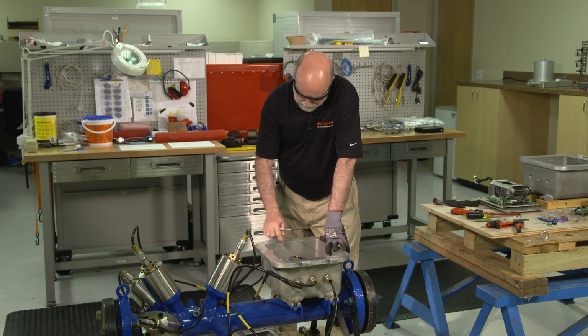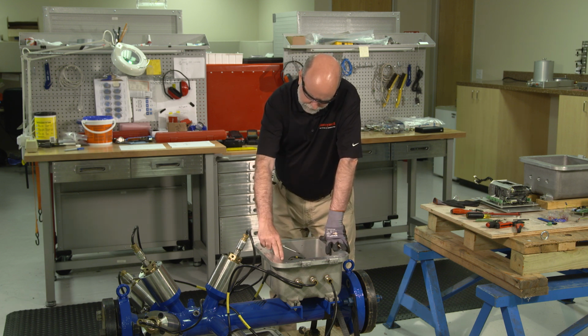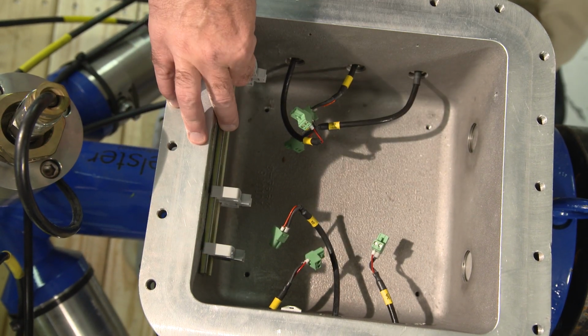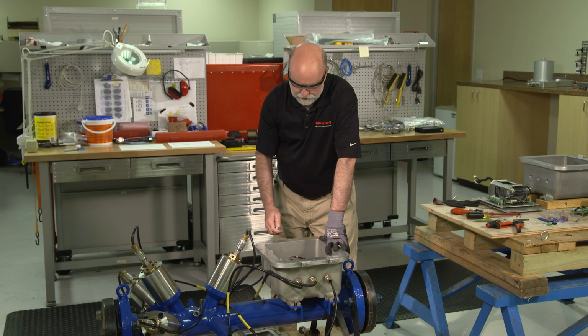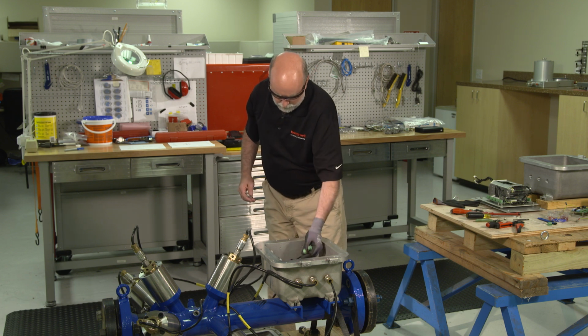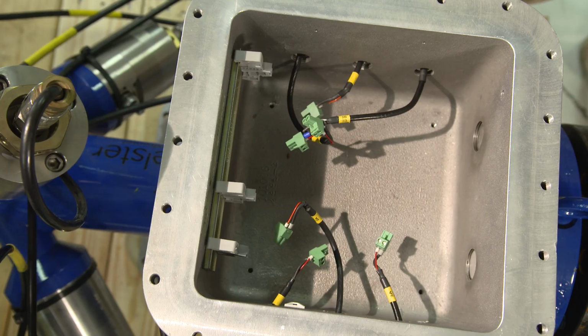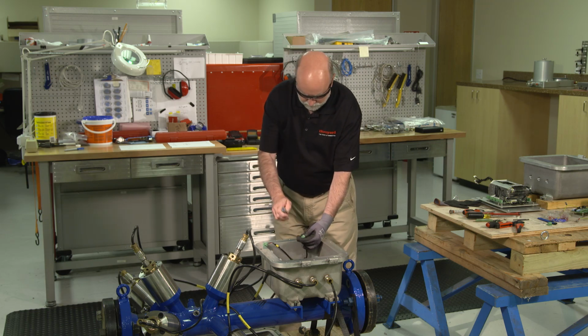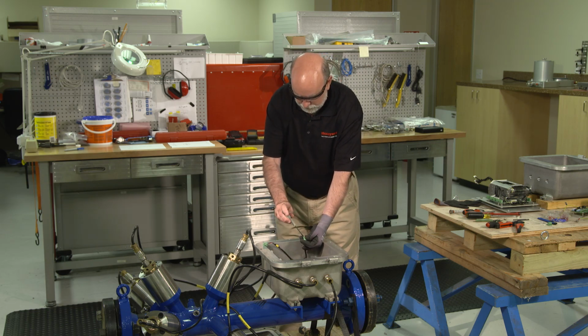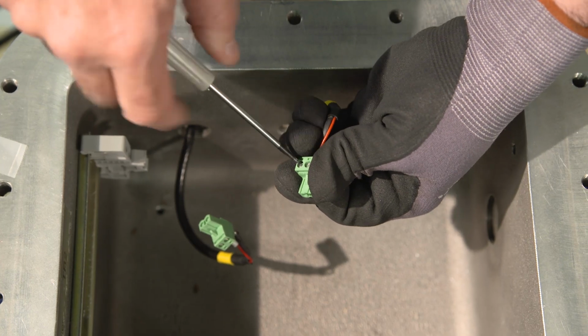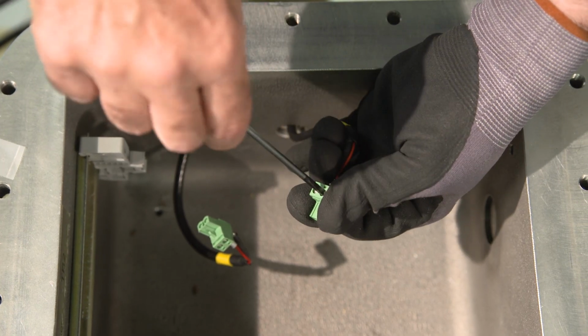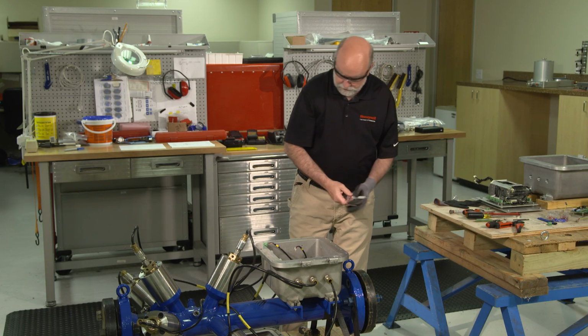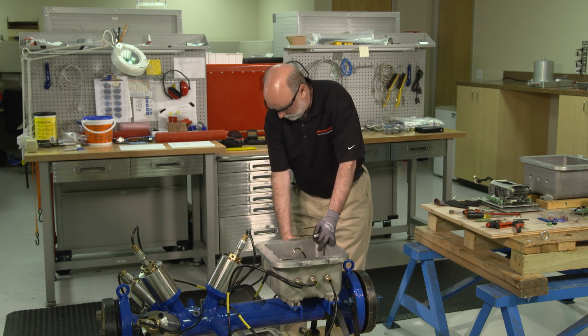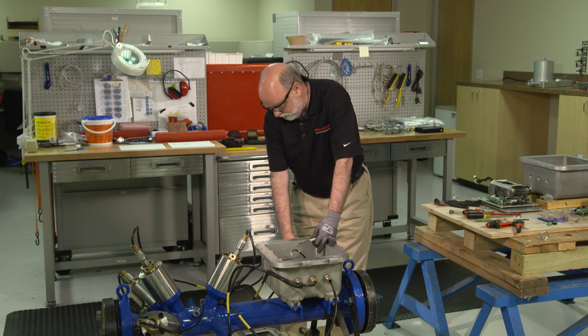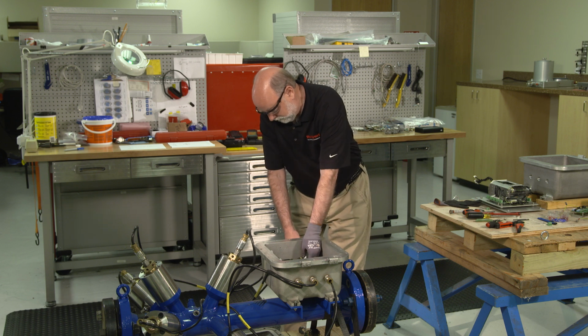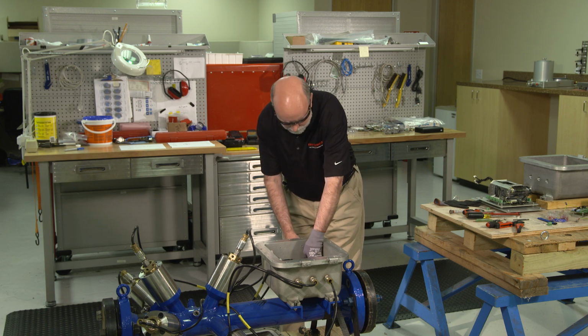Okay, so we're down to just the DIN rail. The separator blocks can remain on the DIN rail. We may loosen those up to facilitate installation of the new one. Notice that we still have all the transducer cables in here. Next step would be to loosen the screws on these 2-pin Phoenix connectors of the transducers all the way around. Just going to show you one for illustration's sake. We need to loosen up the cable glands so that we can pull these cables back out of the box.